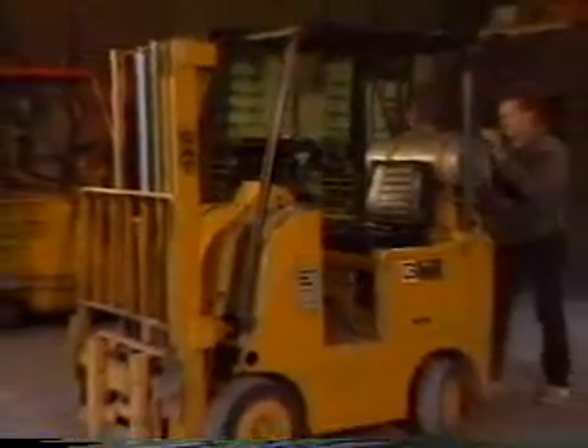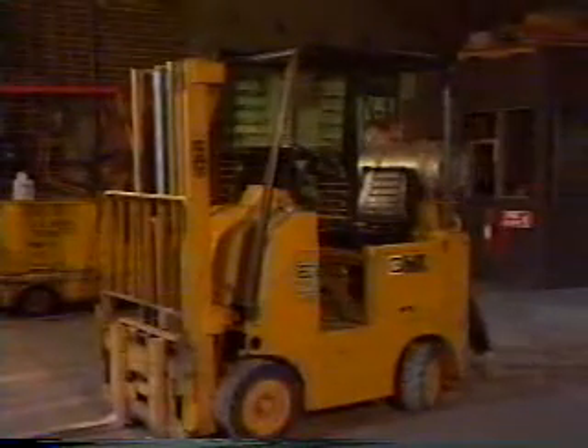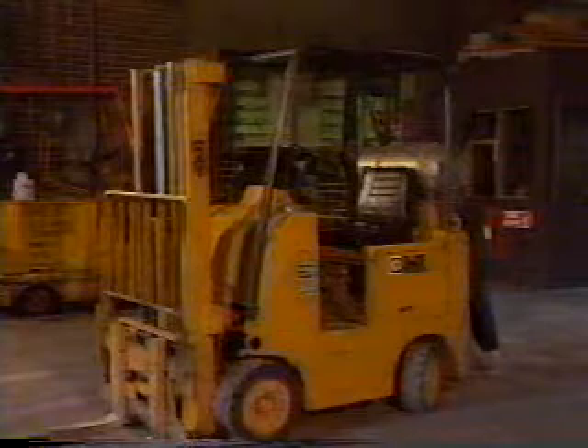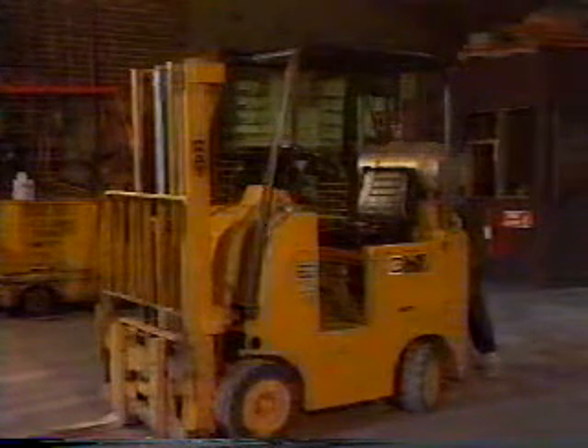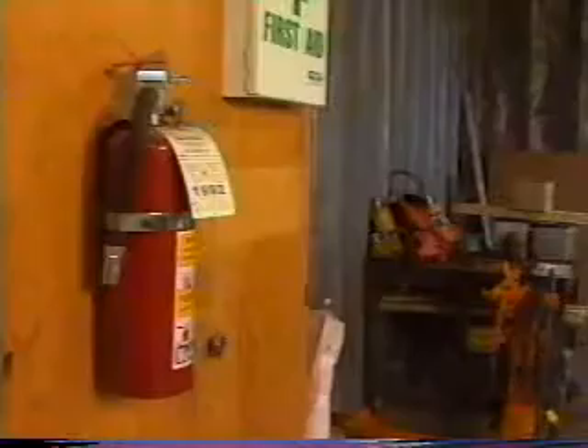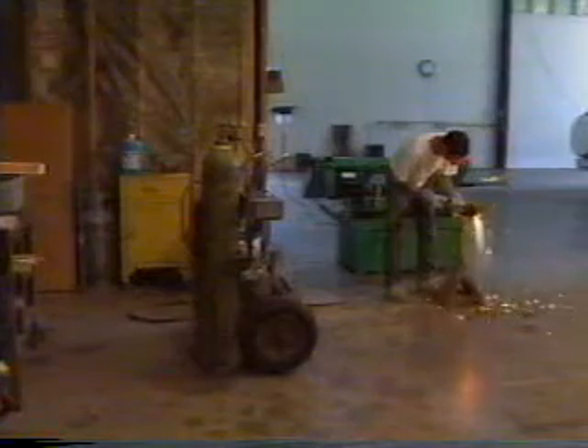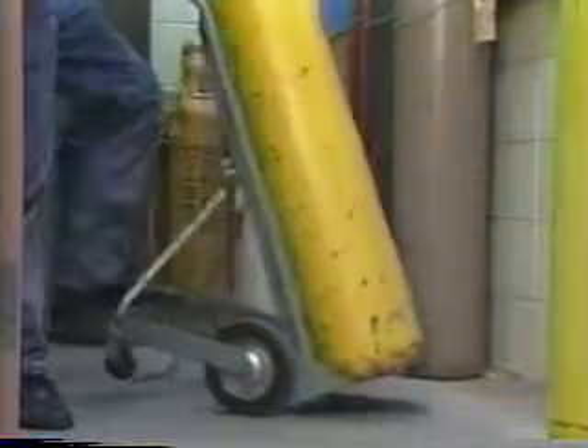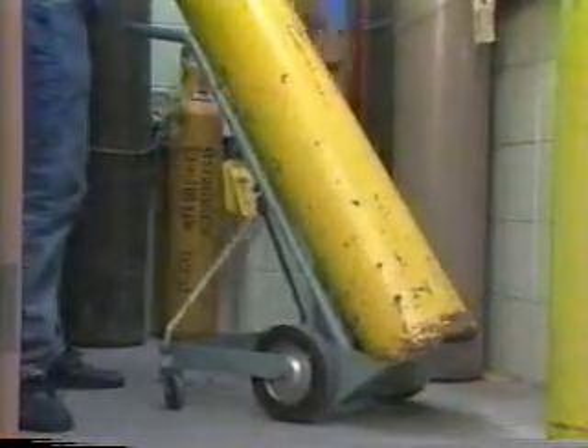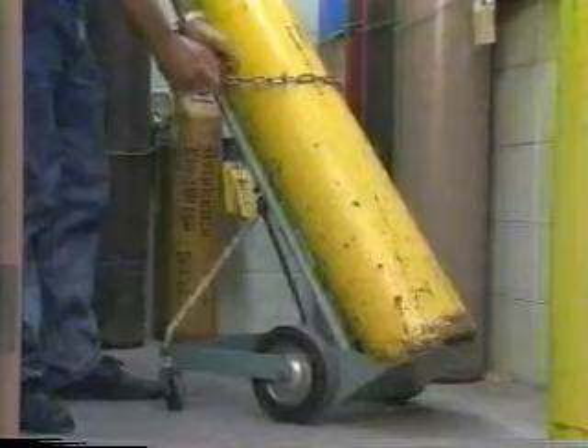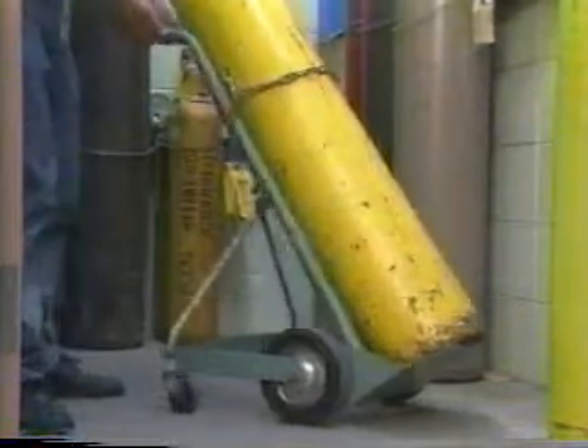All forklifts and other devices used in material handling should be refueled and serviced outside or in an area away from manufacturing or storage facilities. If welding procedures are performed in the work environment, an in-house permit system should be in place. An important part of this permit system is to make sure a fire extinguisher is available during the welding process and for at least 30 minutes after the job is completed. In addition, gas cylinders used for welding procedures should be securely held in place, and extra cylinders should be kept in a separate area away from the welding site.